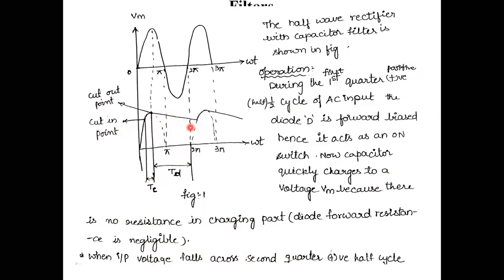The period up to the next cut-in point, we can treat as discharging time. From the cut-in point to the cutout point, I am going to treat that time as charging time. And from the cutout point to the next cut-in point, I can treat that time period as discharging time. That is the basic difference between charging time and discharging time.